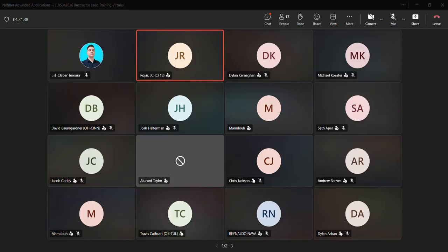It sounds like they're using the elevators for different things. You've got your normal occupants going up and down these floors, but during emergencies, are they using the elevators as well? Is this why they do these manual overrides? They have the manual overrides because we have a lot of inmate vandalism, so we need to maintain the safe, orderly operation of the facility. And since it's a detention facility and we have a 24/7 manned station next to the fire alarm panel, we've gotten variances to override it.